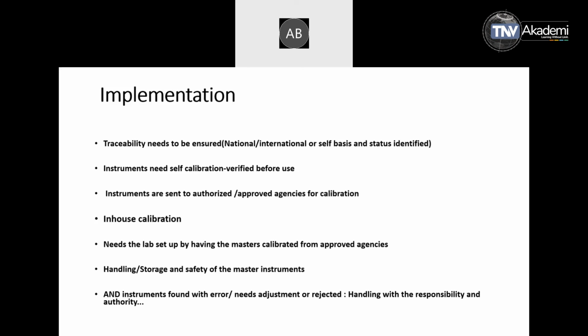What to do when an instrument has an error? Sometimes when we get it from outside agencies who are doing calibration, they find an error, but that error should be under the acceptance limit as per the IS specification for that particular instrument and for that particular process. Within that error, they can accept the calibration done, plus or minus 0.1, 0.2, or 0.1 kg per centimeter square, or 0.1 millimeter, or whatever is the requirement of the instrument and the condition of the machine. So with that error, we should be clear.